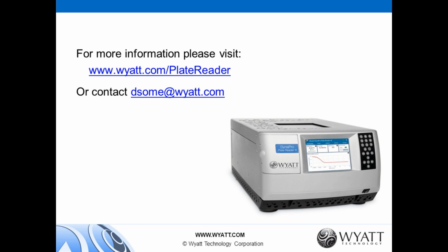All right. Next question. Could we use the DynaPro Plate Reader 3 to optimize buffer screens for protein complexes? Sure. Because you're measuring the size of the protein and its molecular weight, if you have a buffer which leads to dissociation, you'll see that immediately in a change in size. If the size changes, say from 5 nanometers in radius to 7 nanometers in radius, that's a pretty sharp change, and we see that very clearly. And you'll see that in the molecular weight as well.